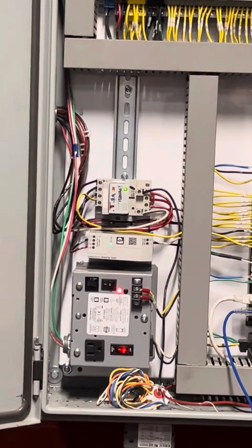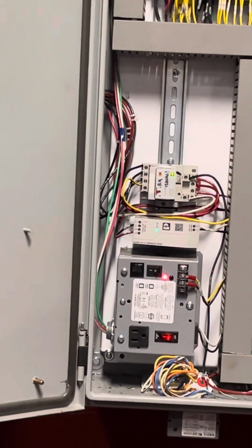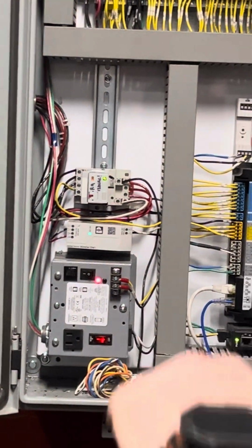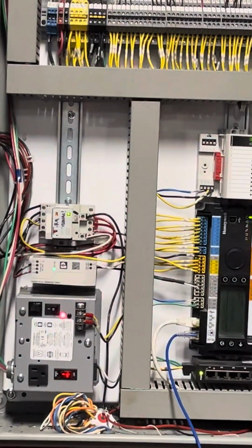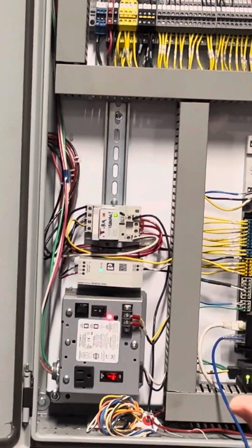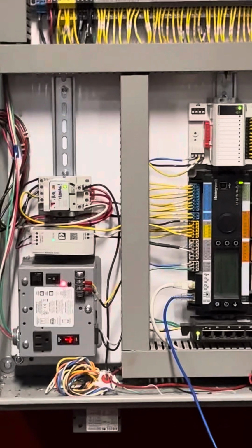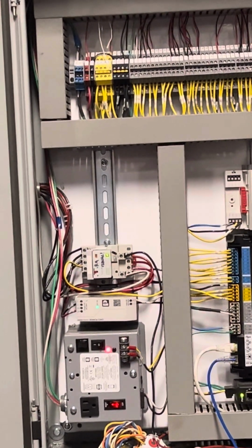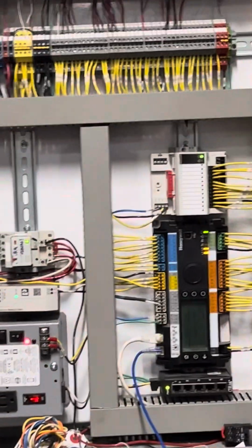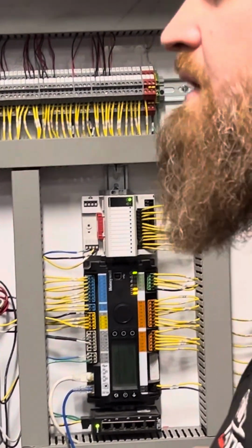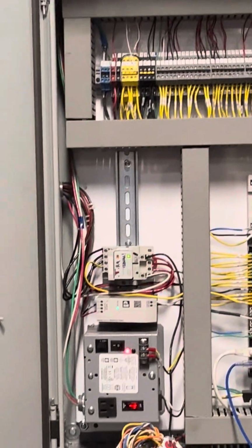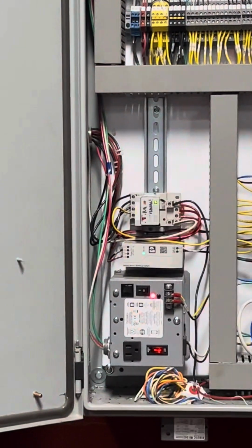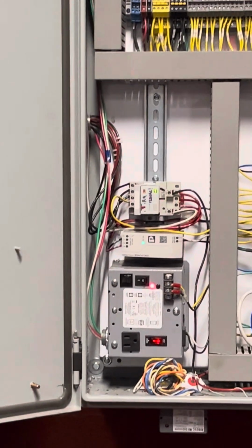You have the local control switch on those boilers, but if you left it in remote and just triggered that on, there's not going to be anything to shut it down except for his controls. Got it. So we usually put those in there because there's not always a local mode on boilers, so it allows you to at least go and then the high limit that's built onto the boiler would then shut the boiler down and you just constantly fire back and forth through that. Since he has the burner control in there, it'll go up to whatever the burner control is limiting it to and then just modulate to maintain that. So if you leave it in remote.